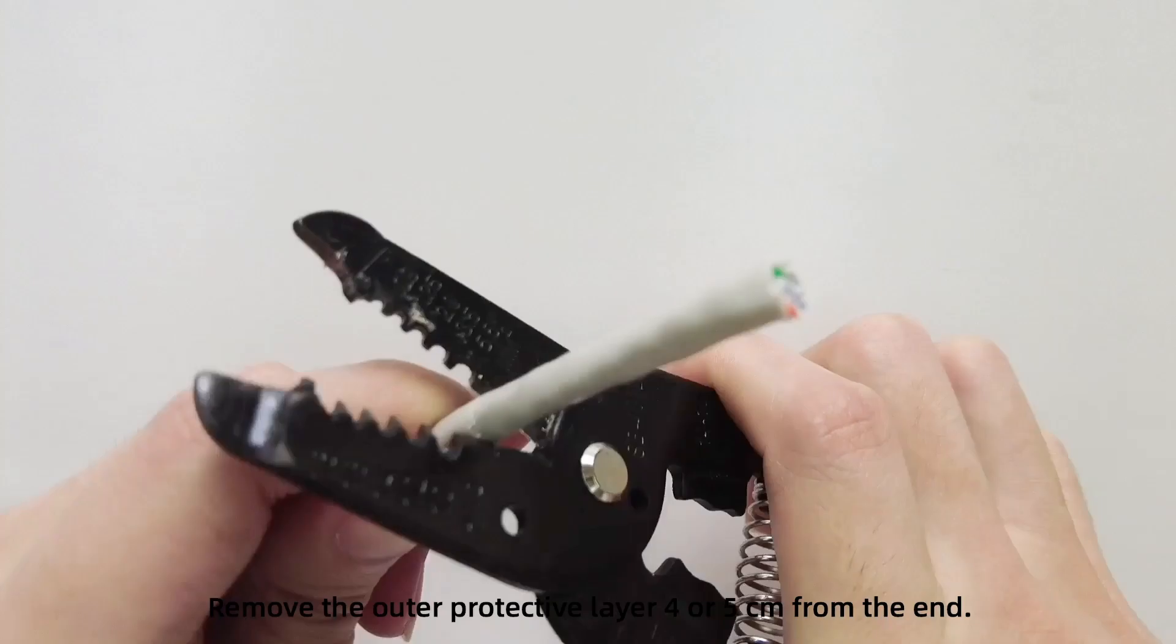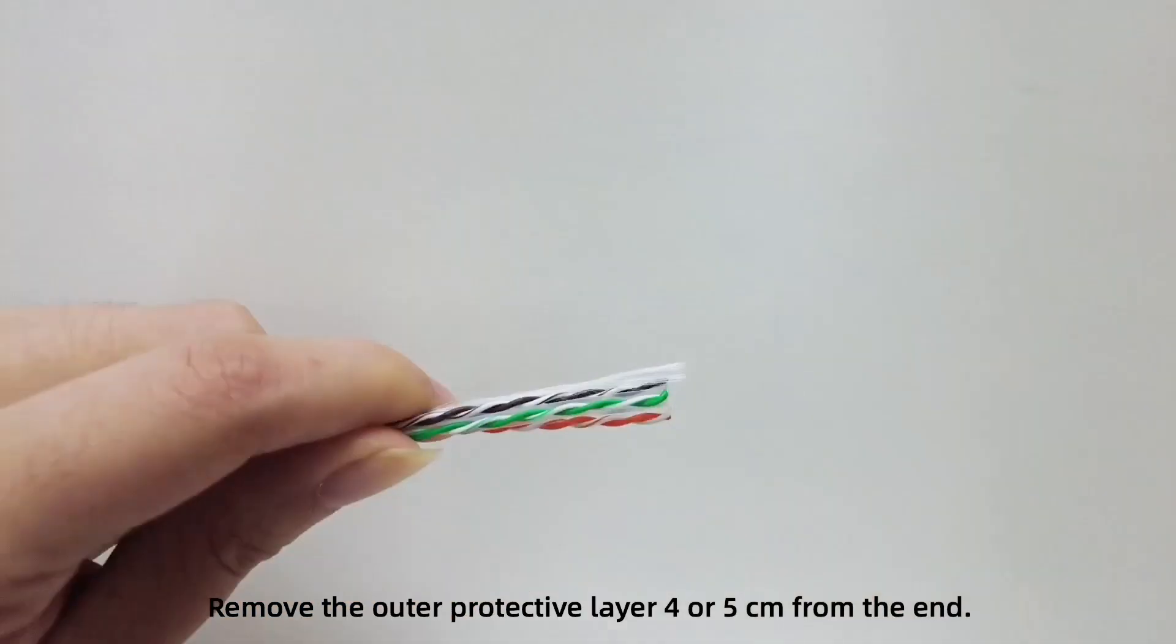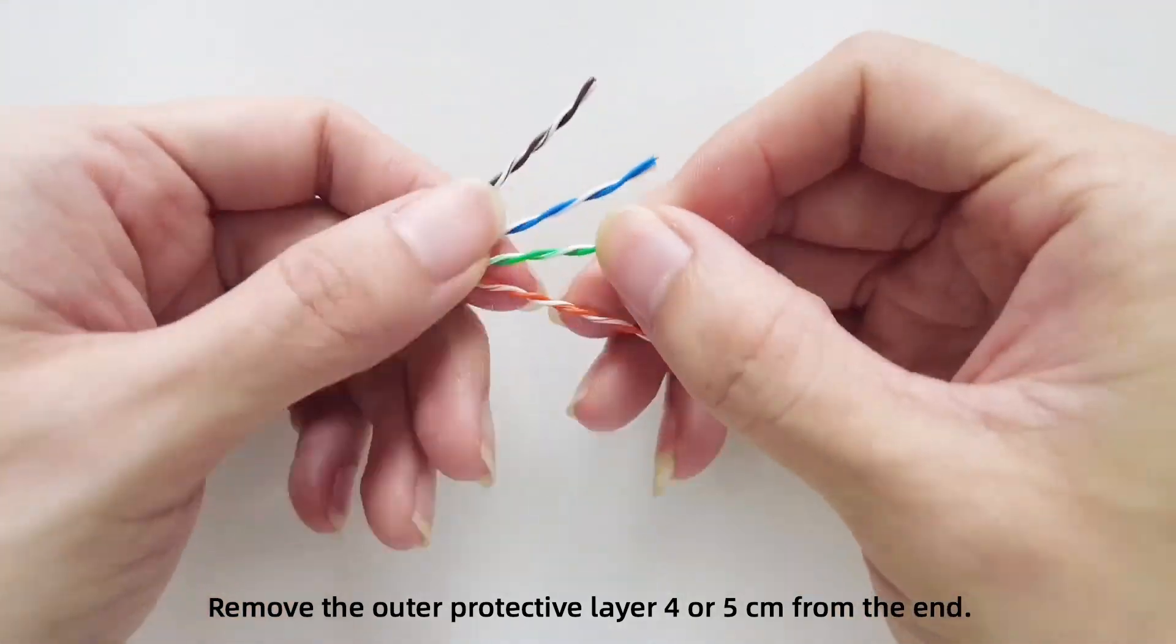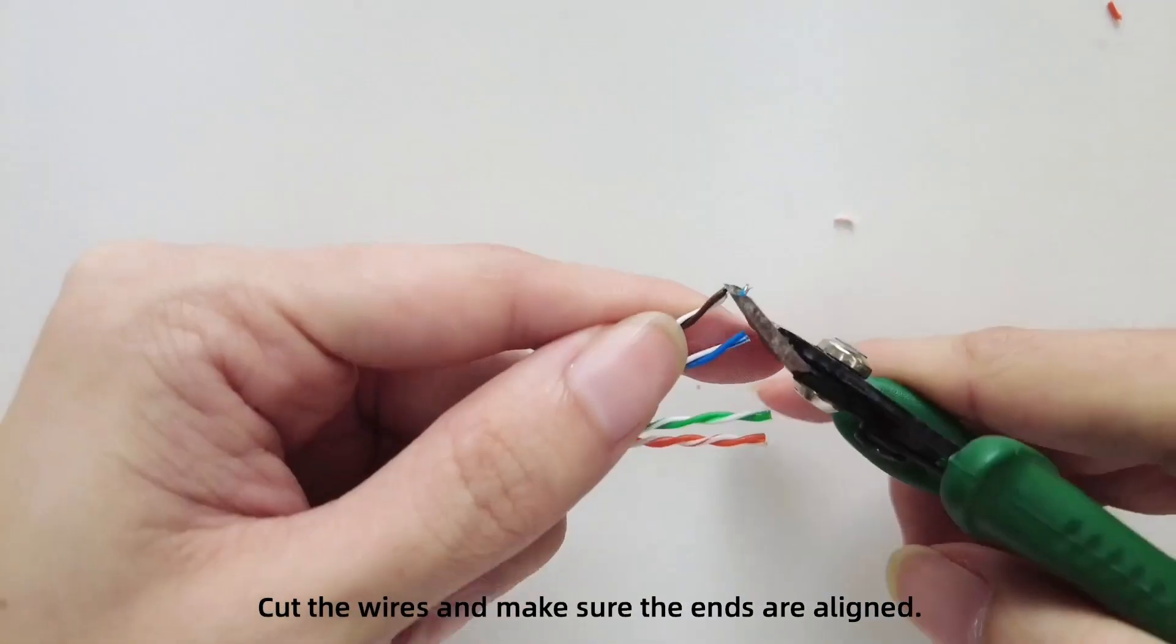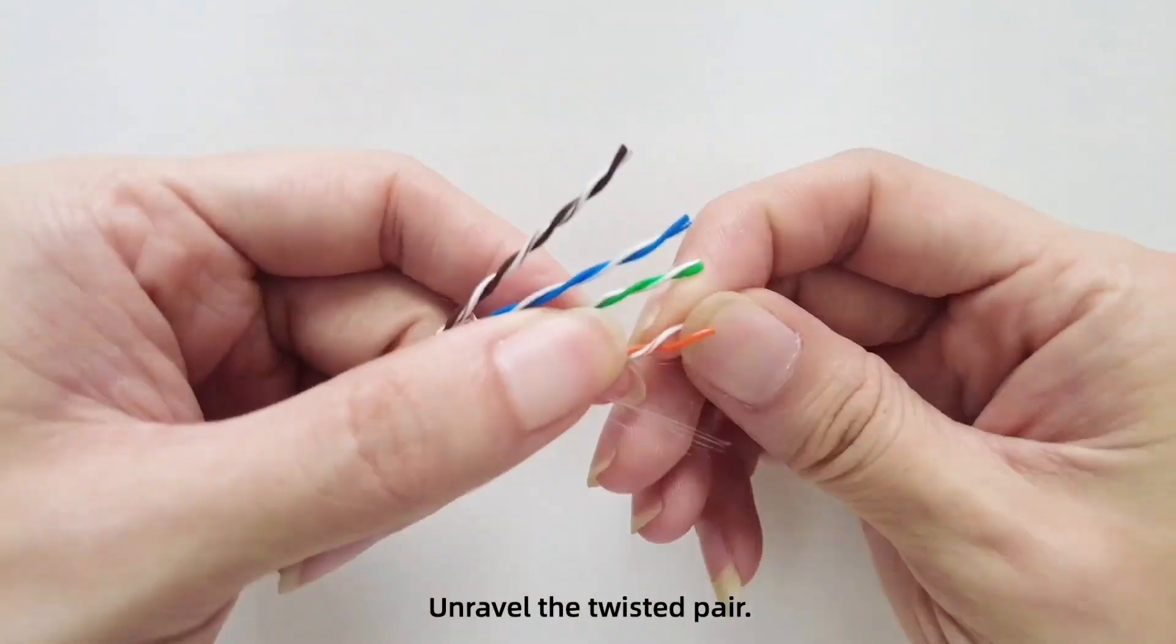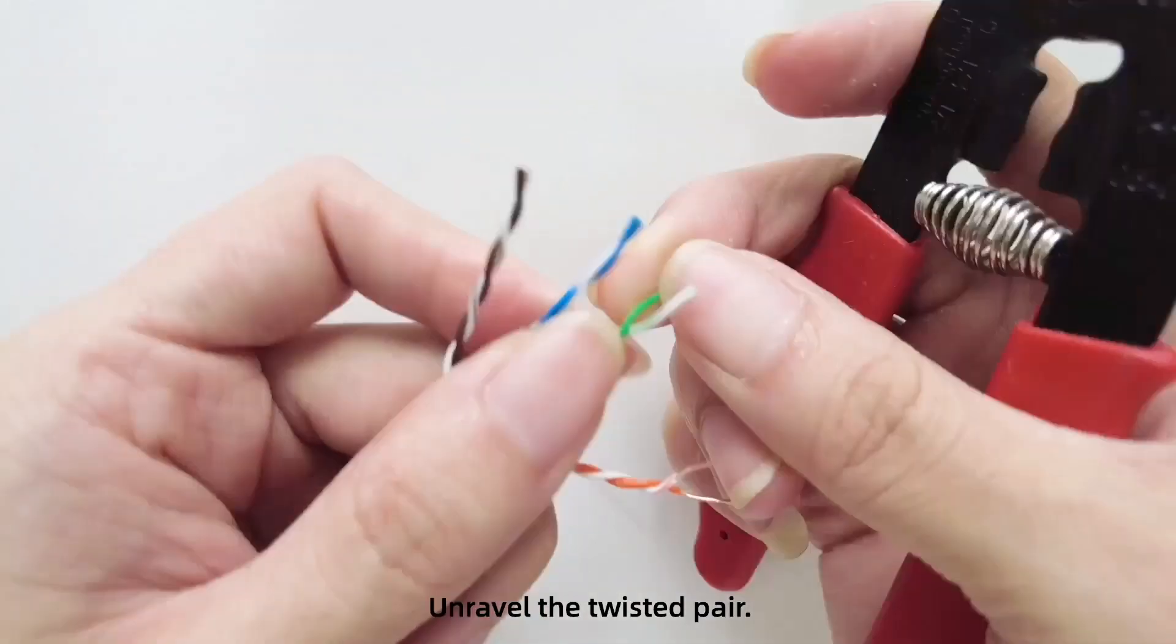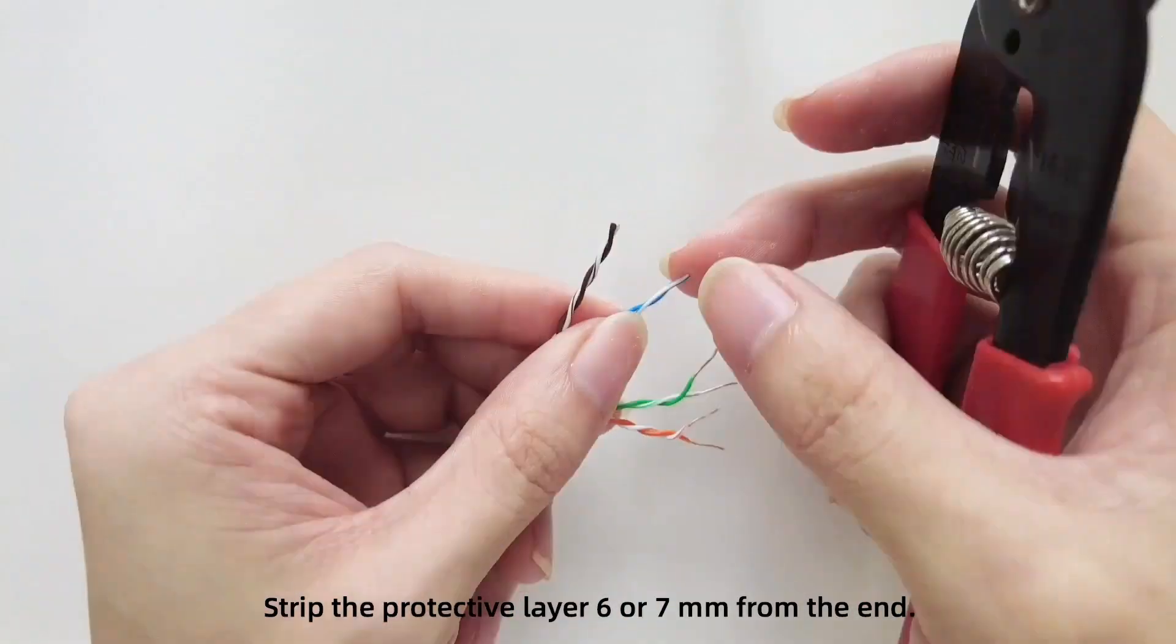Remove the outer protective layer 4 or 5 cm from the end. Cut the wires and make sure the ends are aligned. Unravel the twisted pair. Strip the protective layer 6 or 7 mm from the end.